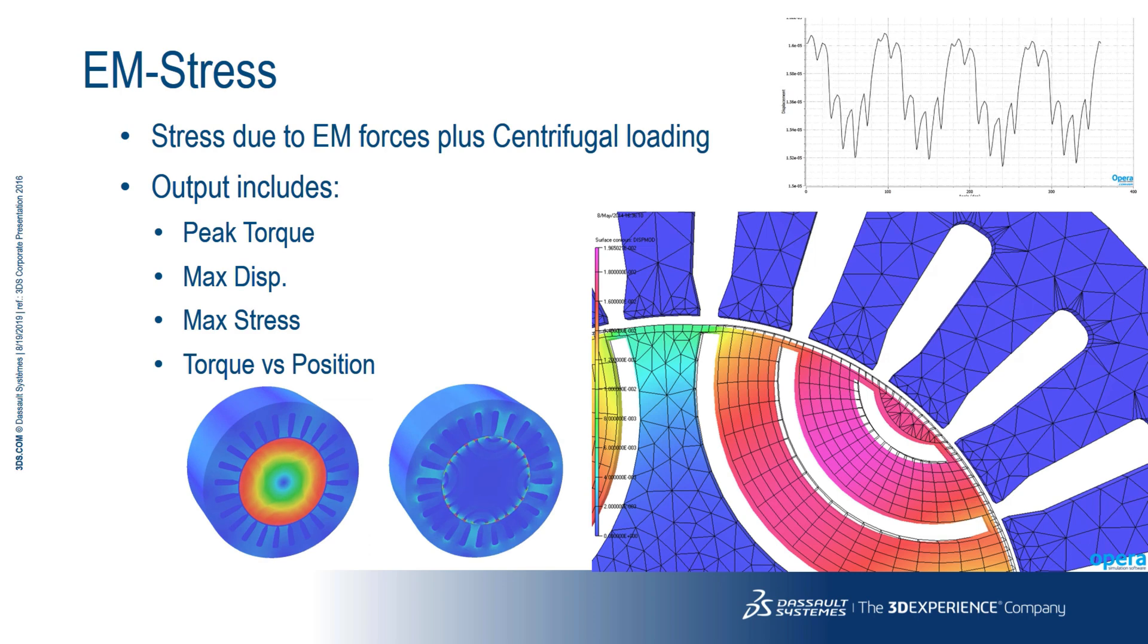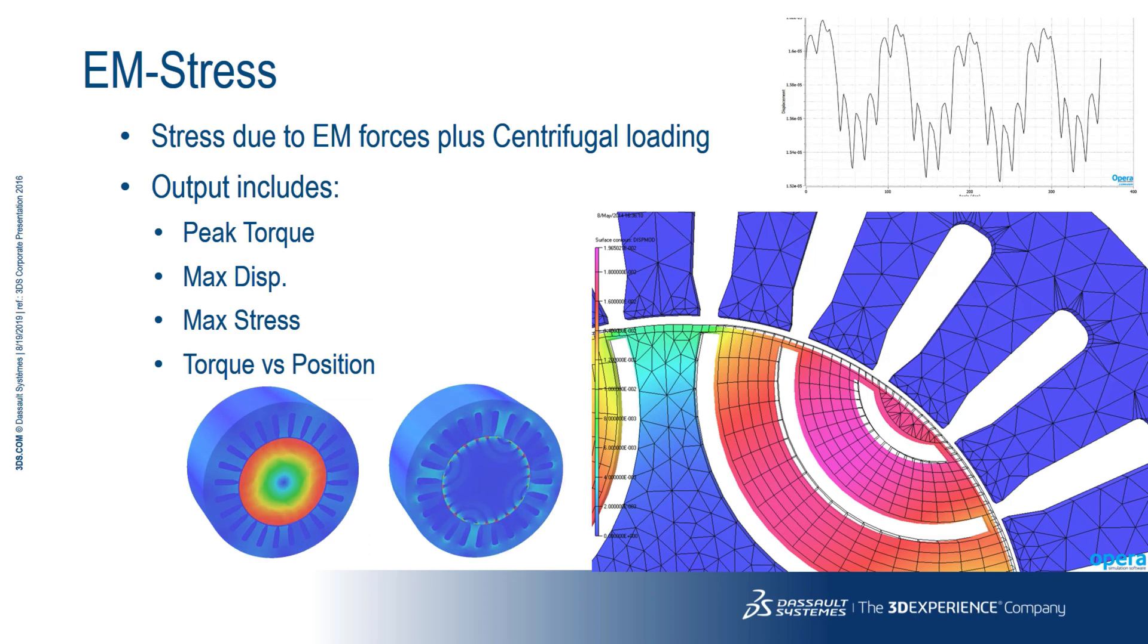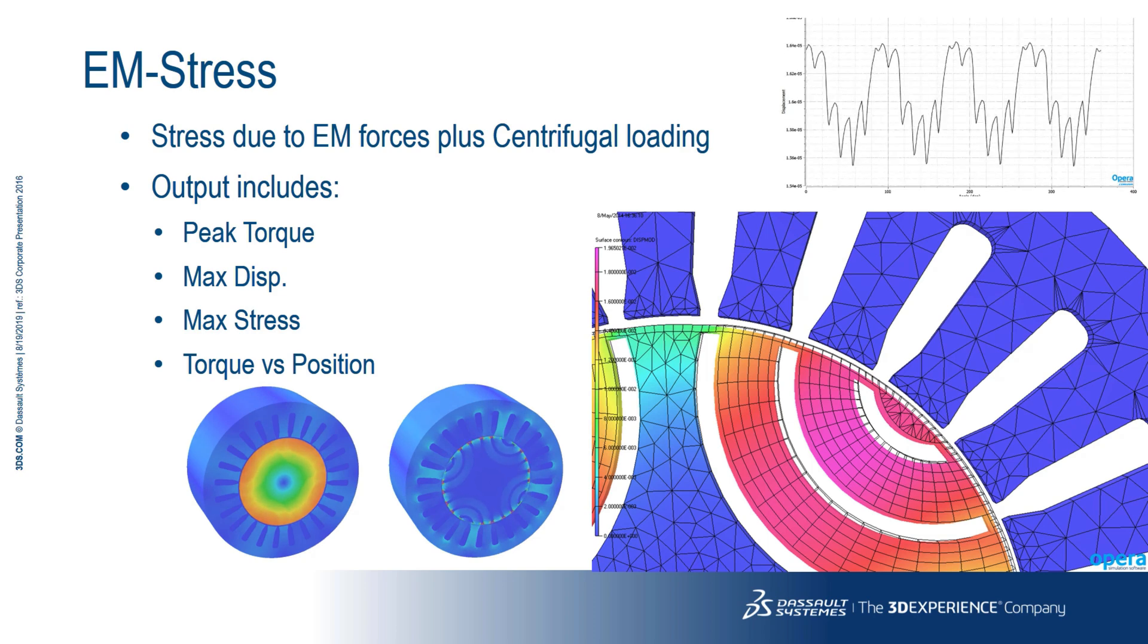The electromagnetic stress analysis creates a series of static jobs for different rotor positions with the stress stage added to each of these jobs. The output includes the value of peak torque, its mechanical angular position, maximum displacement, maximum von Mises stress and the torque versus position curve.